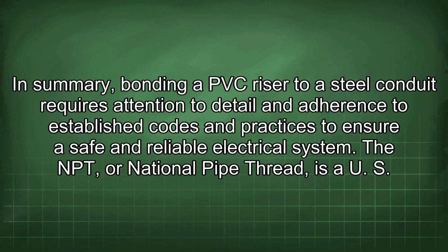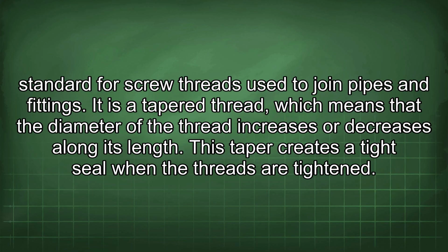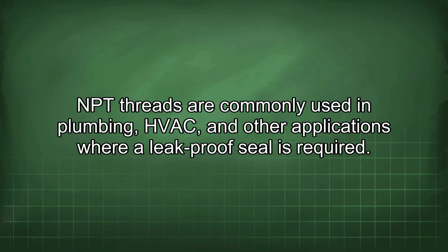The NPT, or National Pipe Thread, is the U.S. standard for screw threads used to join pipes and fittings. It is a tapered thread, which means that the diameter of the thread increases or decreases along its length. This taper creates a tight seal when the threads are tightened. NPT threads are commonly used in plumbing, HVAC, and other applications where a leak-proof seal is required.